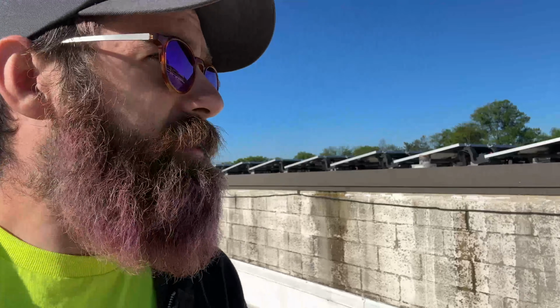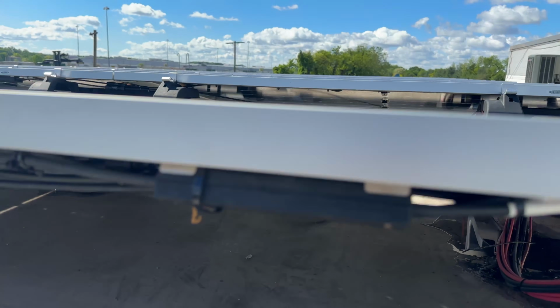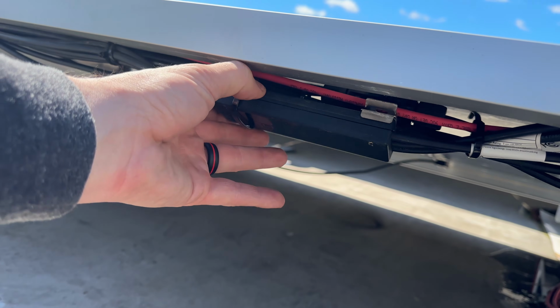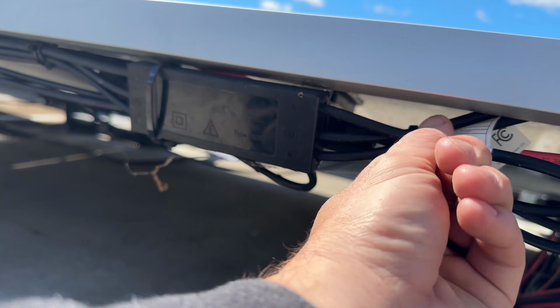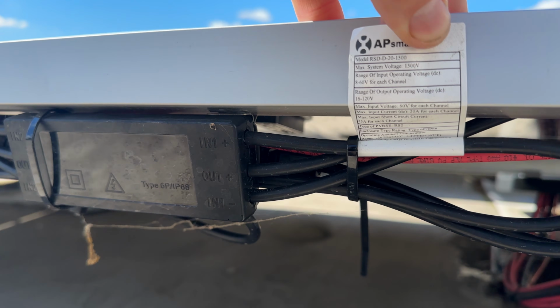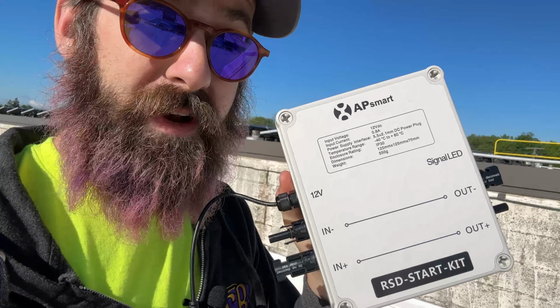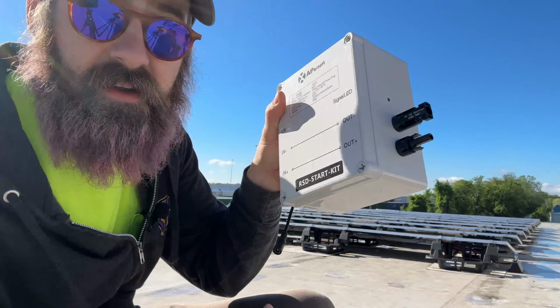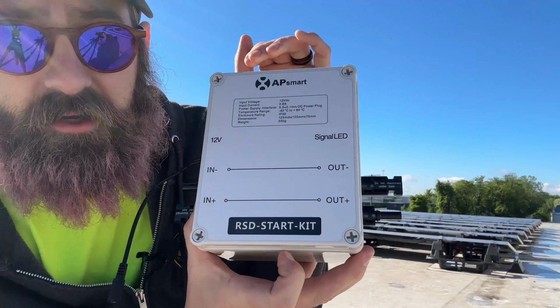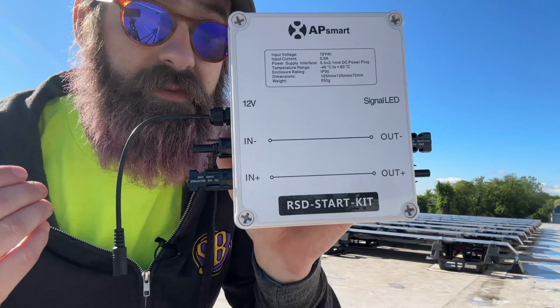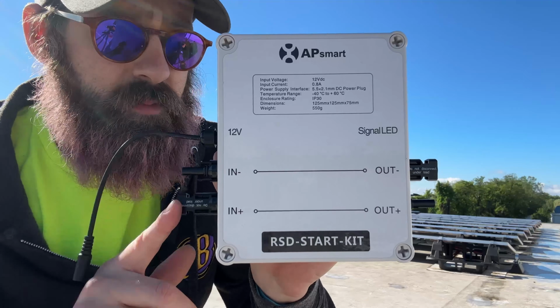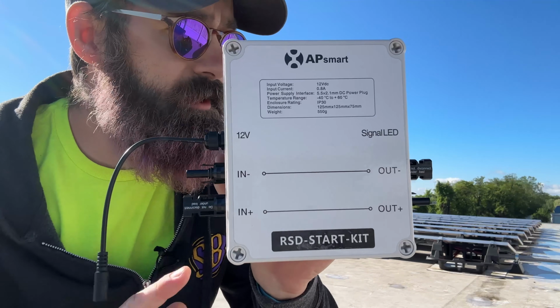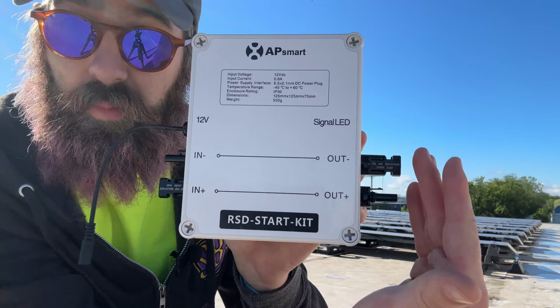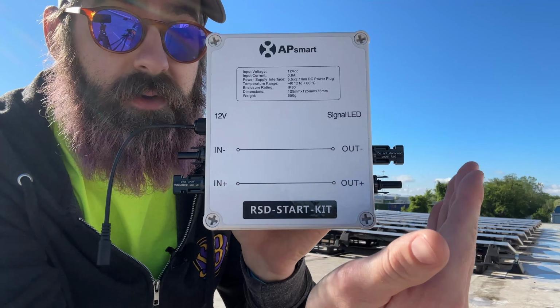In the solar industry, it is generally assumed common knowledge that a system like this, where you have rapid shutdown devices—in this case an AP Smart 2-to-1 RSD—that you cannot curve trace these systems. But I don't think that's true anymore. I have yet to test this, but this AP Smart RSD start kit theoretically lets an entire string's worth of voltage pass through it. You have your inputs here where you put your string voltage, and your output here where you put your curve tracer, and bada bing, bada boom.